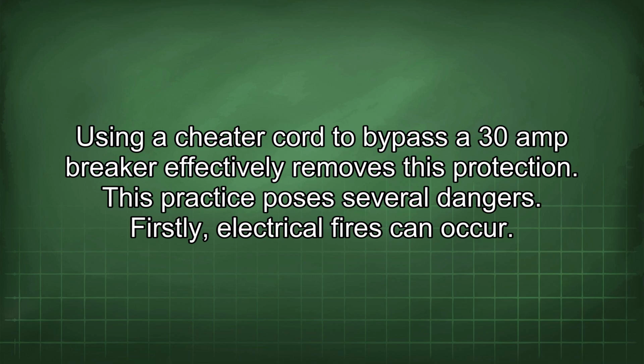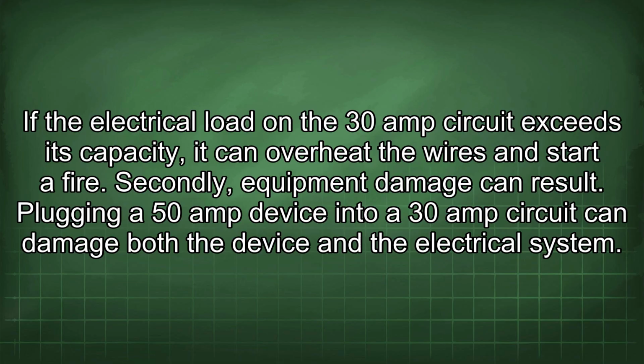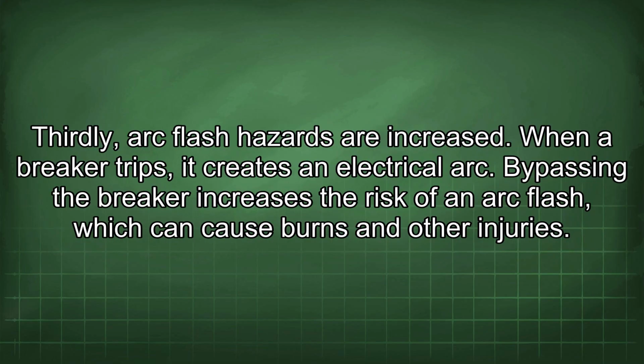This practice poses several dangers. Firstly, electrical fires can occur. If the electrical load on the 30-amp circuit exceeds its capacity, it can overheat the wires and start a fire. Secondly, equipment damage can result. Plugging a 50-amp device into a 30-amp circuit can damage both the device and the electrical system. Thirdly, arc flash hazards are increased. When a breaker trips, it creates an electrical arc. Bypassing the breaker increases the risk of an arc flash, which can cause burns and other injuries.